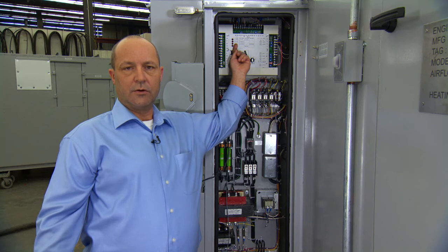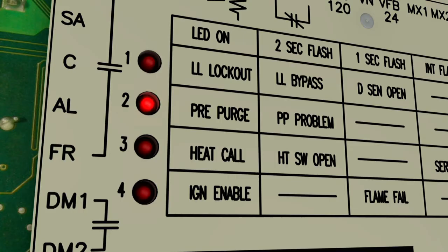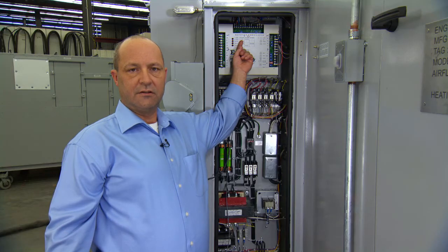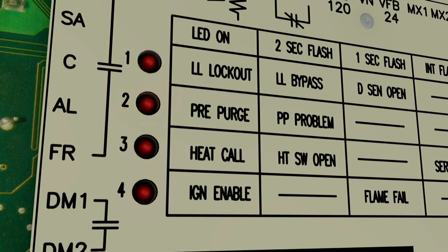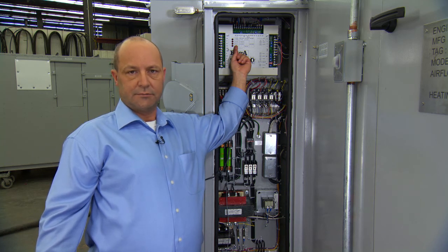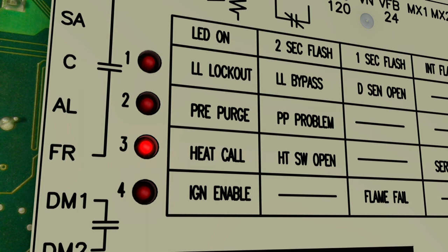Replace sensor. Number 2 light, on steady. This is on in pre-purge mode when heat call is established. 2-second flash. This will happen when there is a pre-purge problem. See diagnostic chart in the DJM-3 manual to troubleshoot. Number 3 light, on steady. This is on when there is a heat call by the discharge air sensor. If equipped with a heat switch, remote or unit mounted, this switch must be closed to give 24 volts AC across terminals HS and N of the controller. 2-second flash. This will happen when there is no 24 volts AC between terminals HS and N. The heat switch will be open. Intermittent flash. This indicates the controller is in service mode by having dip switch 5 on.